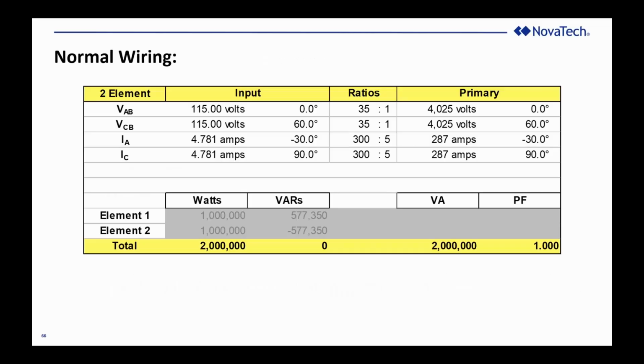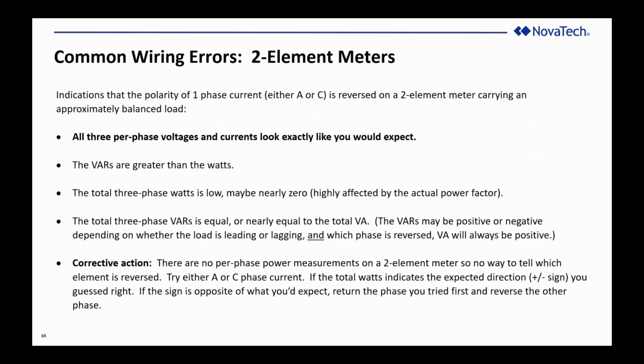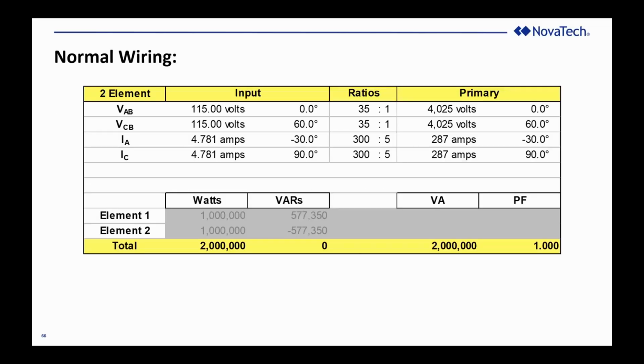So here's my two-element wattmeter. This is what the calculator shows me. Notice that I'm looking at VA to B and VC to B, not VB to C. So that's why this is going to have a 60-degree phase shift and not a 120-degree phase shift. So what I've done here is switch the polarity of one current. Okay, so we have switched the current from a 30 degrees, oh, this is the normal wiring. That's right. I was saying this is right.